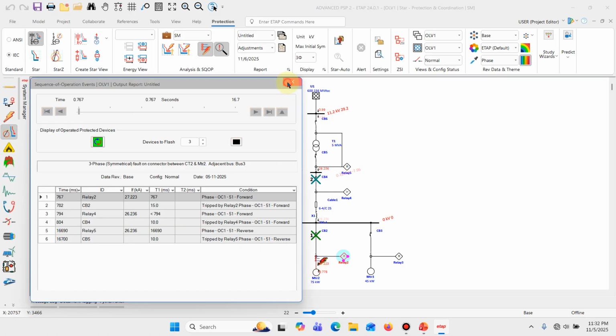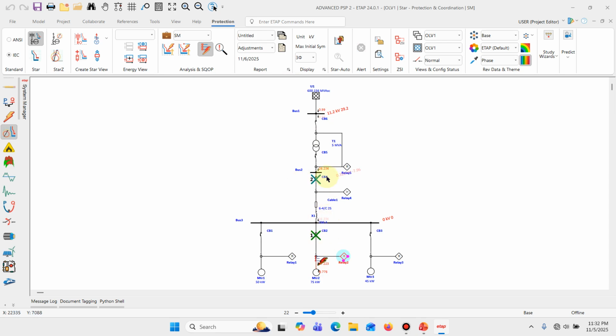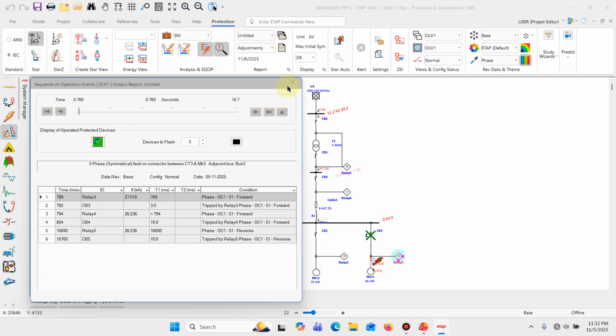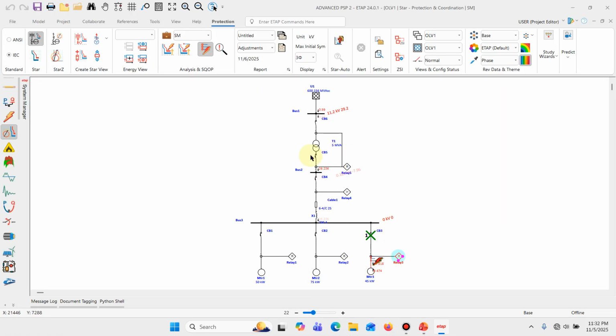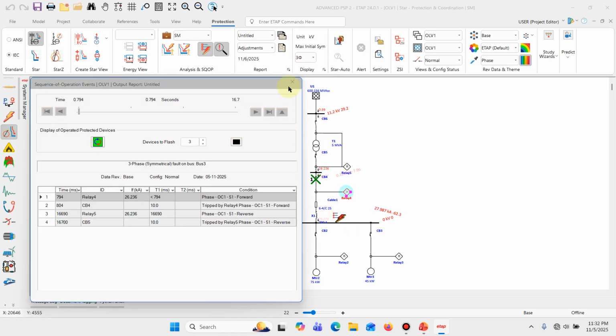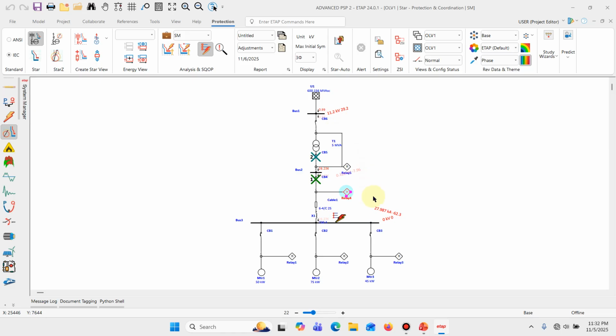Okay, we can see 1, 2, 3. All right, let's put the fault on this motor. Okay, so we are inserting 3 phase faults at various locations, and we can see that the selectivity is there. Let's have the fault on this bus bar. Okay, so we can see it's working in the right sequence.